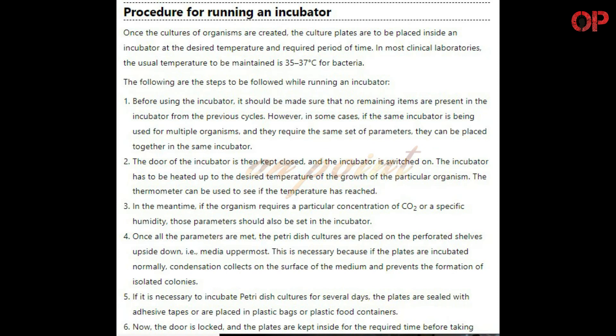Procedure for Running an Incubator: Once the cultures of organisms are created, the culture plates are to be placed inside an incubator at the desired temperature and required period of time. In most clinical laboratories, the usual temperature to be maintained is 35 to 37 degrees Celsius for bacteria. Step 1: Before using the incubator, it should be made sure that no remaining items from the previous cycles are present. However, if the same incubator is being used for multiple organisms requiring the same set of parameters, they can be placed together. Step 2: The door of the incubator is then kept closed and the incubator is switched on.